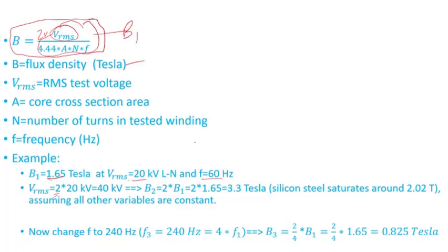So two times B₁ is 3.3 Tesla. Silicon steel saturates around 2.02 Tesla. That means this here will cause the core to saturate and cause problems—basically overheating and other things. Assuming the other variables are the same, which means the cross-section area and the number of turns are the same...